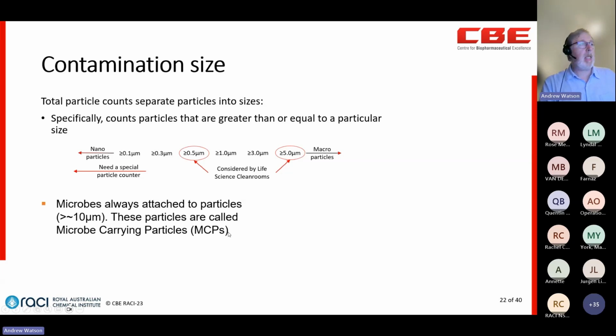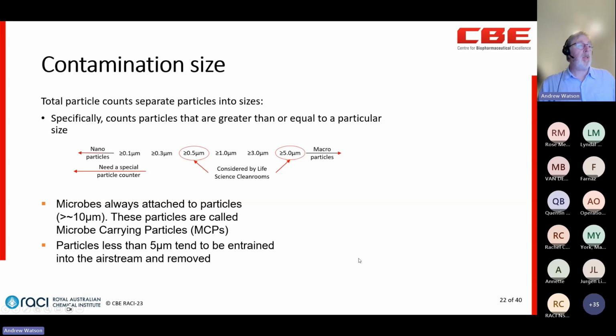A key thing to understand is that microbes, and to another extent viruses, don't hang around as single entities. They move around because they're attached to a piece of skin or some sort of process material that's been dislodged, and they float around attached to those. A key thing to remember about particles is that particles that are 5 micron and greater tend to settle to the floor, whereas the smaller particles will be easily entrained into the airstream and removed. So most of the contamination you're worried about, because in life science you're worried about microbes, is generally on the floor. It moves around when people walk around the space and kick it up into the air.